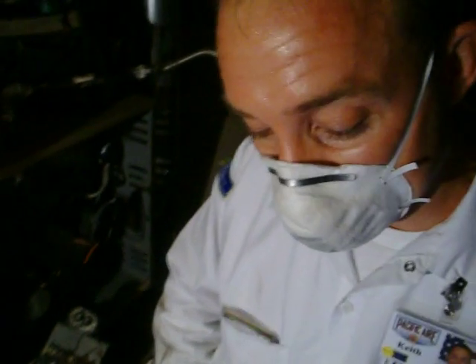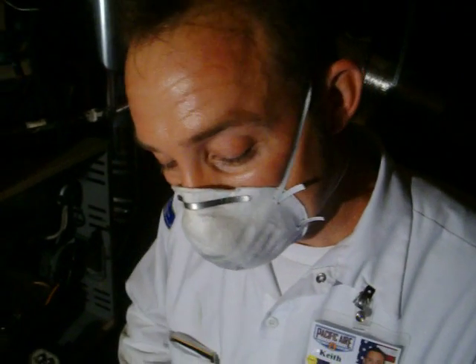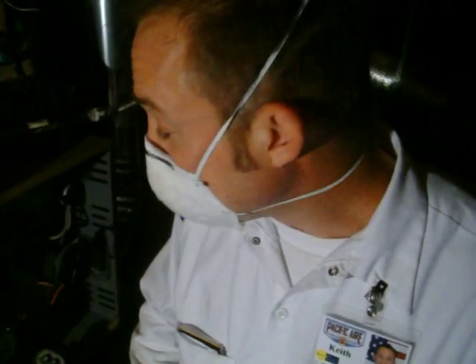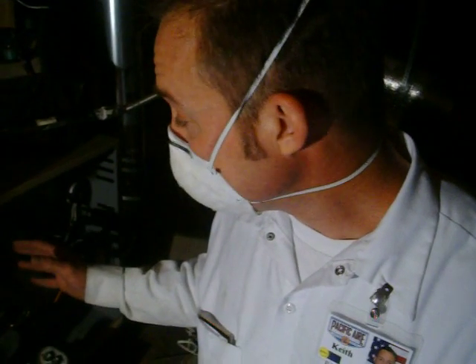And what am I looking at here? That's a picture of the evaporator coil. Now, some of the debris that has bypassed the filter has started to accumulate on the interior portion of your evaporator coil. That's not good. No, that's not good. Basically what that does is reduce the capacity of the system and possibly bring about a situation where you can overheat the heat exchanger.